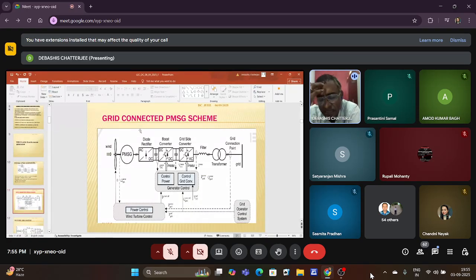Now, to avoid the field variation, to avoid the field converters, another scheme which is in use is the PMSG. Instead of an externally excited synchronous generator, we use a PMSG, permanent magnet synchronous generator. Now, the permanent magnet synchronous generator has another inherent difficulty: its field excitation is fixed, because the permanent magnet strength is fixed. This generated voltage is rectified, sometimes boosted if required, or the boost converter can be avoided if not required, and then there is a fixed frequency converter, then a transformer and the grid.